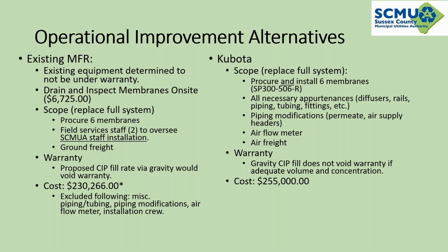And then the other thing was that the data package that was provided didn't track all the required O&M parameters that were required to determine if it was a faulty piece of equipment or faulty operations. So it's kind of a gray area there, but unfortunately, what was provided with the equipment did not meet what was required for their warranty.